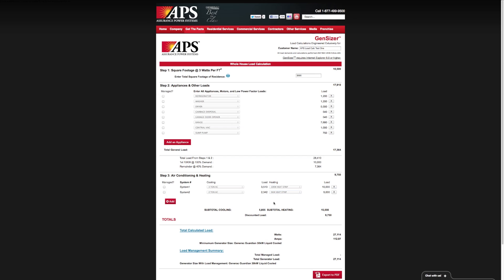The National Electrical Code actually requires you to take the greater of your cooling and heating loads, and this Gensizer tool takes that into account. Now that we've done that, you can see a summary of the total calculated load. We're coming up with 27,000 watts, just over 112 amps.